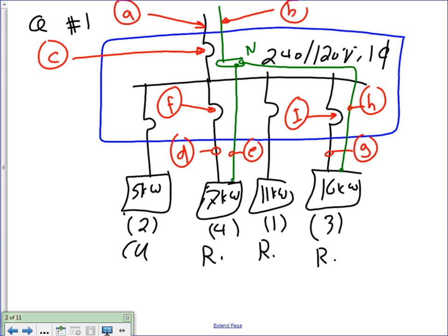If you don't remember this, just go to 310.15(B)(16), the table. If I tell you what's the insulation rating of TW, and you don't know it's 60, go to 310.15(B)(16). You see where the temperature rating, look underneath it and see where does TW sit under which column. Does that make sense, Joe? That's how you find the insulation for that particular conductor. The multiple choice or match.